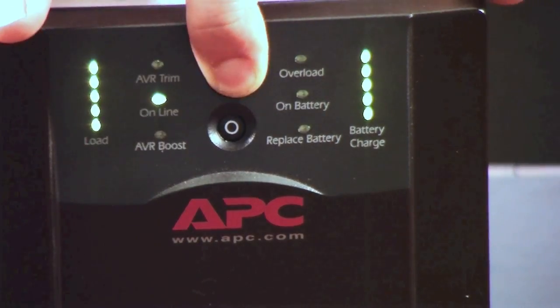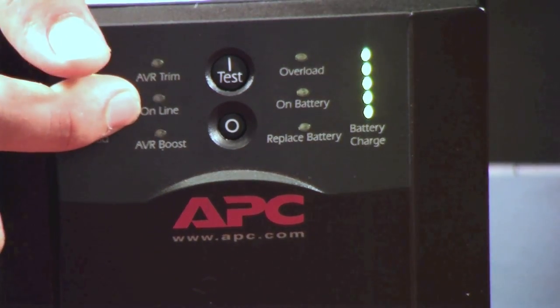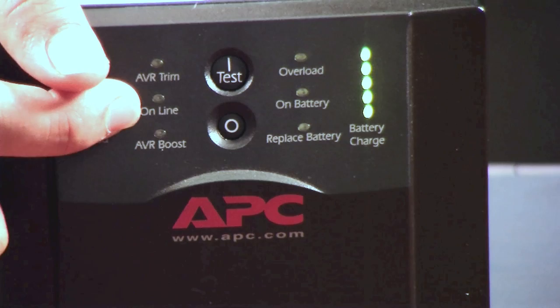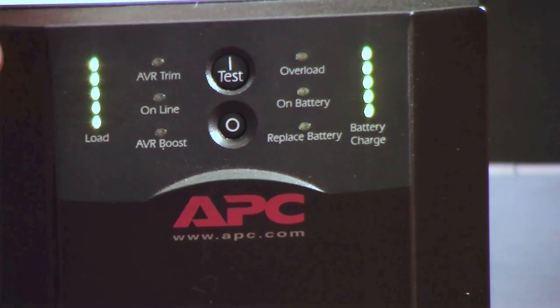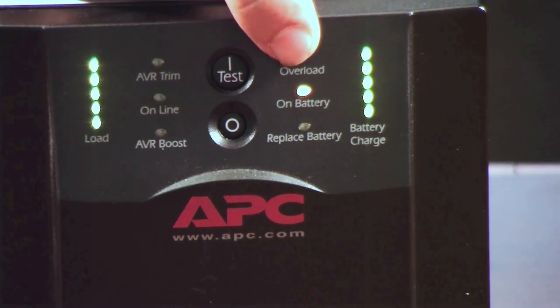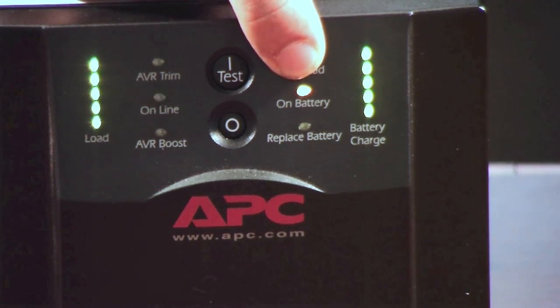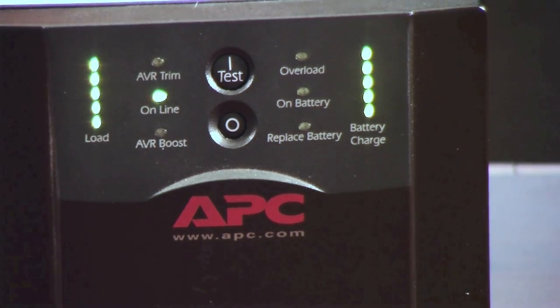So when you first turn the unit on, what's going to happen is the online light is flashing, and it's going to flash for about 10-15 seconds. Then the unit's going to go to a self-test where you see right here a little battery light came on, and once the unit has gone through its self-test, it's going to flick back and the online light is going to stay on and lit.